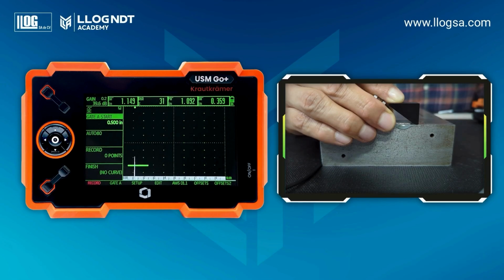Once the maximum amplitude is found, adjust the gain so that the echo reaches 80% amplitude. In the record function, press the right navigation key to save the first point. This will be our reference level.